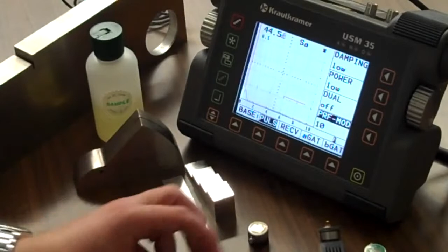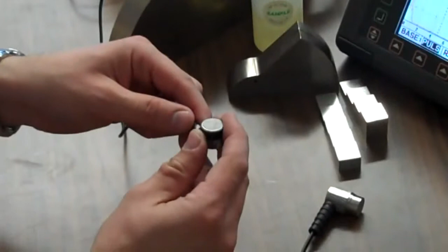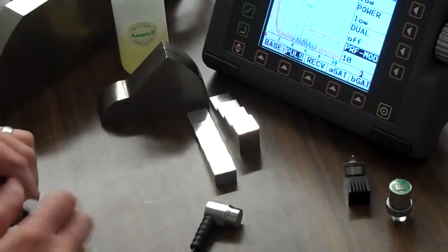So, just a little bit about that. Let's go with a single element transducer first on a 3-inch range. Just going to hook in the BNC connection, or microdot connection. You might see questions floating around that ask which of the following is most common: BNC or microdot? So those are out there. There's our BNC hookup, here's our microdot hookup. If you see a bunch of spiking right there, that's telling us the transducer is alive. So we hook that up.